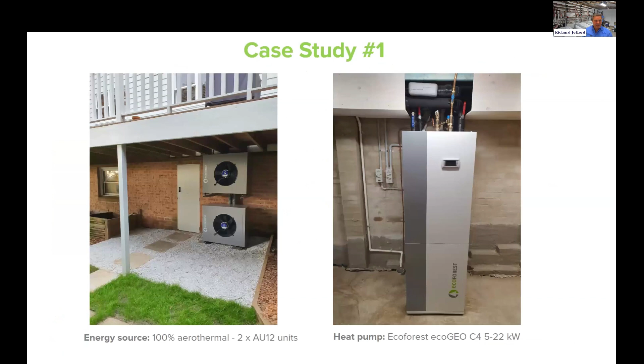This house had radiators in it. We were able to add some fan coils into the system, giving it a separate split system to provide cooling as well as hot water and heating. With forced air, the capacity of radiators is generally undersized from when a gas boiler was initially installed, with that very high temperature, 75-plus degree design.